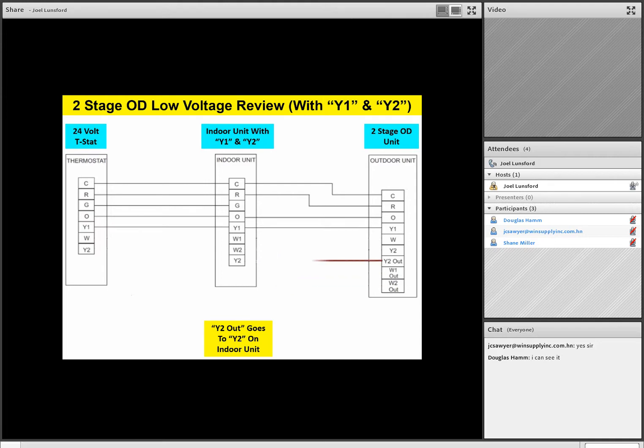So in this scheme or scenario, what we're doing, we're allowing the two-stage outdoor unit to actually stage or call. When you get a second stage call on the outdoor unit, it's going to allow that outdoor unit to bring on second stage airflow inside. So this is a very, very common wiring scheme, again, with an ECM product, if you've got the indoor unit that has the capability of a Y1 and a Y2 terminal.